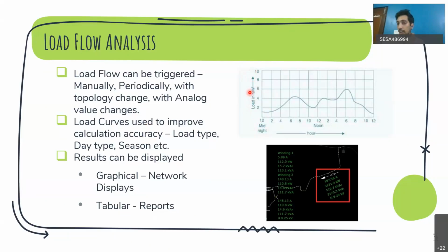So when you are running load flow analysis on a particular DT, first it will try to identify which load curve it needs to use for calculation, then at that particular point of time, what scaling factor it needs. Those kinds of things it will calculate, and based on that, load flow is run. So the more load curves you have, the more accurately you are denoting the load condition, and obviously the output will be more accurate.